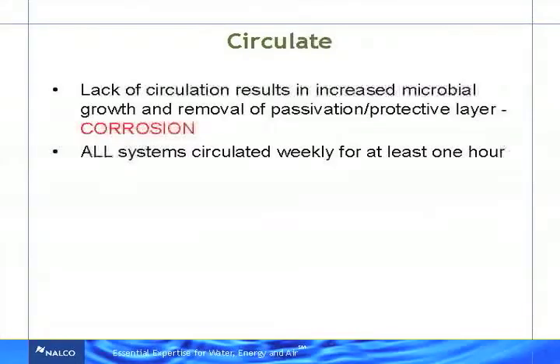So all systems need to be circulated at least once a week for an hour. And when I say all, I mean every chiller, every tower that's flooded, every piece of pipe, every filtration system. I see that a lot. People have a sand filter that they don't run in the off season, and then when they turn the sand filter back on, it's full of goop because it's just full of bacteria. So make sure you circulate every piece of equipment you have that's flooded for at least an hour a week. And that'll solve 90% of your problems in the off season. I call it a duty cycle. Make sure you have a duty cycle.